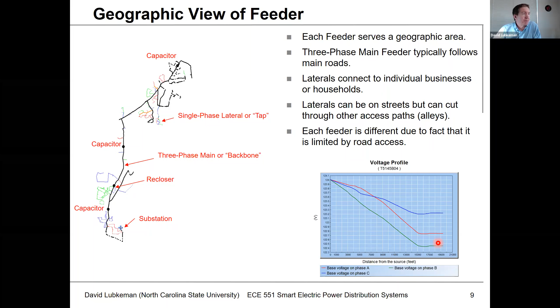What we're going to worry about is what happens with the voltage, because if I regulate the voltage at the substation, by the time I get down to the end, the voltage is going to drop. This is actually from a circuit analysis program showing how the voltage changes from the top of the feeder down to the bottom. If the voltage gets too low, we can't properly supply load. This is a big thing we'll talk about in this class - the calculation of this voltage drop.